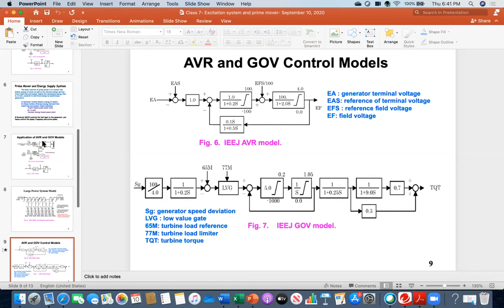So the governor model here is somewhat longer. The final goal is to produce the torque or mechanical power, that is fine, but you see there is some feedback, and there are some specific things like 65M meaning turbine load reference, 77M meaning turbine load limiters. In that way, it is complicated. Different systems might have different models. But what I am telling you is that these two, this governor model and this AVR model, whatever the system is, even if you analyze that 10 machine system, you can still use this AVR and governor model. It will give you pretty good stability results.